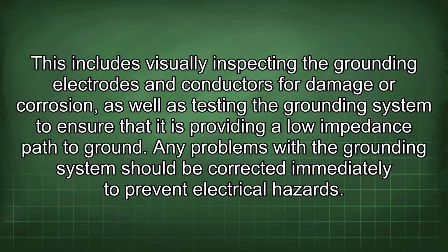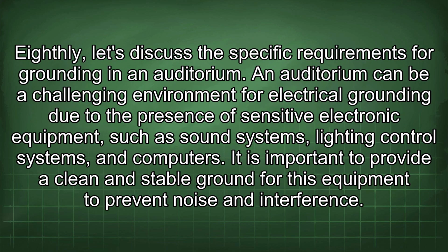This includes visually inspecting the grounding electrodes and conductors for damage or corrosion, as well as testing the grounding system to ensure that it is providing a low impedance path to ground. Any problems with the grounding system should be corrected immediately to prevent electrical hazards. Eighthly, let's discuss the specific requirements for grounding in an auditorium. An auditorium can be a challenging environment for electrical grounding due to the presence of sensitive electronic equipment such as sound systems, lighting control systems, and computers.